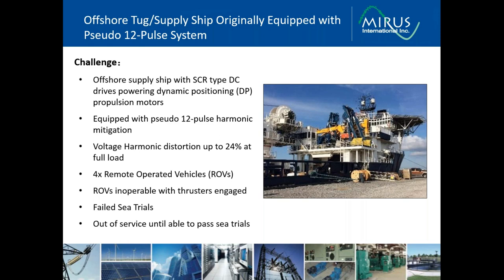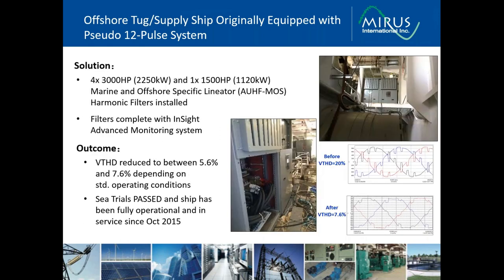Problems included loss in navigation, operational issues such as component failures in the crane controls and in the remote operated vehicles. This occurred especially while they were operating in dynamic positioning mode, which is where the propulsion transformers are in their highest operation. Voltage distortion in that mode exceeded 24%. A system-wide vessel review was conducted to determine the cause of the equipment failures, and a solution was offered to replace the phase shifting transformers with passive wide spectrum harmonic filters.